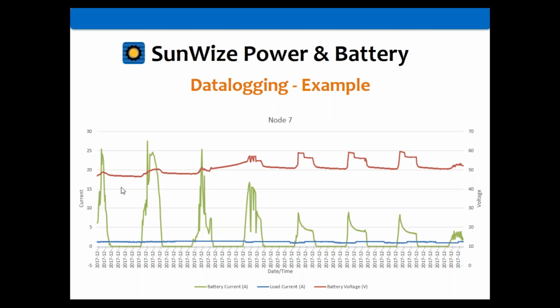But we realized we were having a problem with the solar array. You can see the solar array current isn't quite right. As it turns out, they went out and inspected the solar array and found that some of it was not connected correctly, so they did not have the full solar array. They had partial, which is how they were able to limp along, but they did not have the full array.